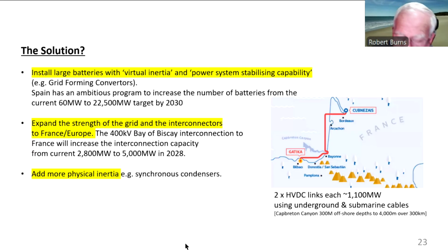The solution, how do you fix that? You can't run back and install 20,000 megawatts of coal-fired spinning alternators. Well, the first thing you would do is install large batteries with what's called virtual inertia and also power system stabilizing capability, such as grid forming converters. Now, virtual inertia means that when the frequency does fall, the battery can supply extra power to slow that rate of change. The inertia actually affects the rate of change of the frequency fall. It doesn't solve the problem, it just slows that rate. But they can also whack out extra power, and they can also have power system stabilizing capability.